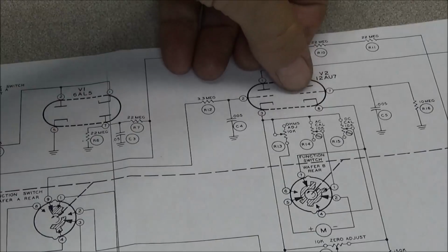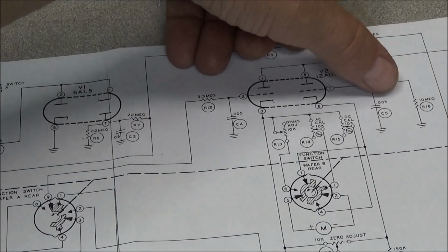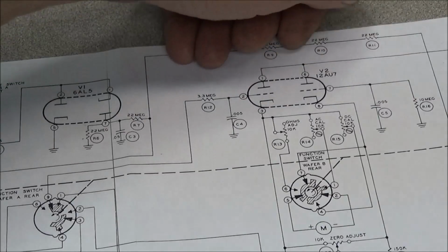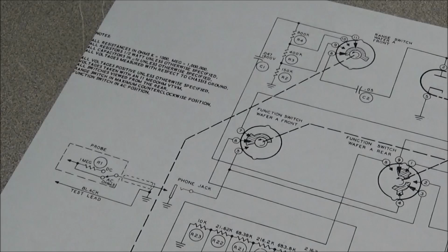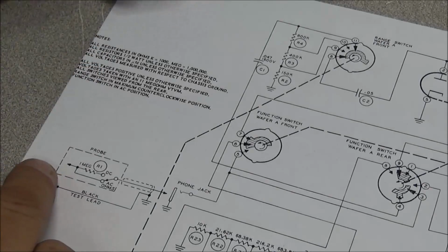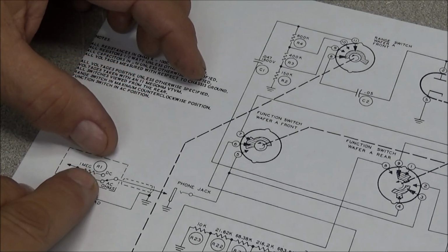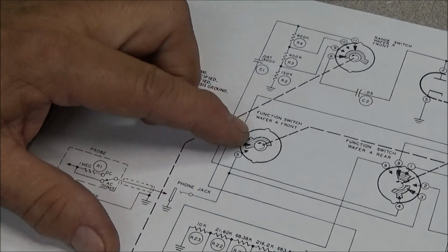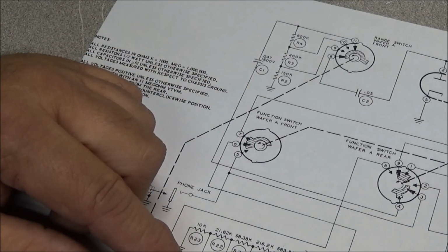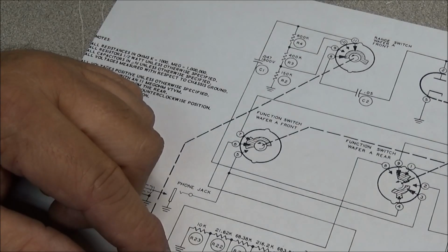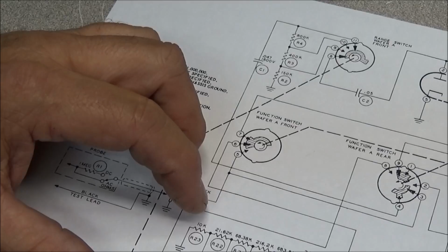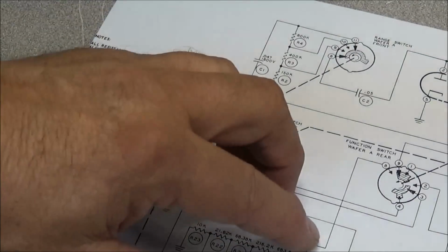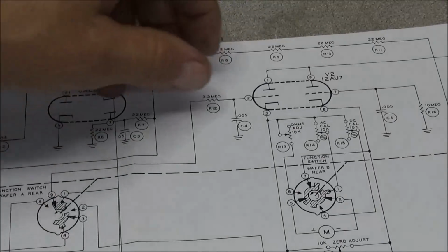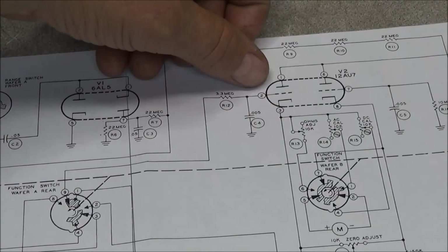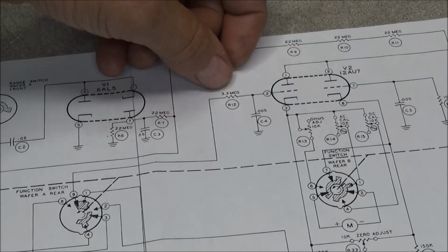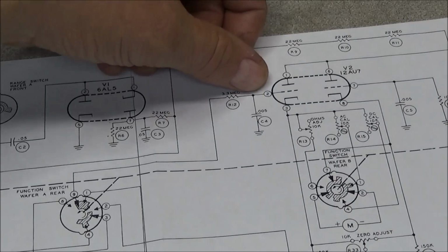And if you look at one side, pin 7 grid has a fixed bias on it. So if you're testing DC voltage, it's going to come in through your probe, go through your 1 meg ohm resistor, and it's going to go through your function switch, and then down to your range switch, where it'll go through the correct precision resistor for that range that you have it in. But it winds all the way back up here to pin 2 of the 12AU7 through this R12 resistor, which is a 3.3 meg.